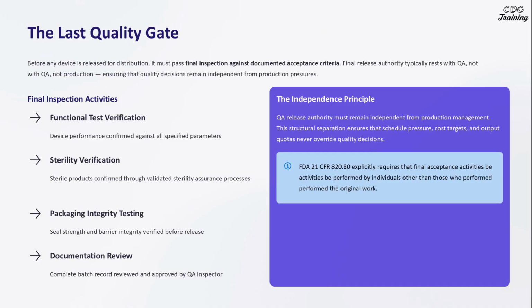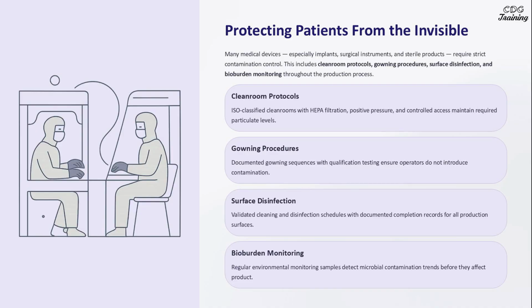Before a device is released, it must pass final inspection against documented acceptance criteria. This ensures that quality decisions remain independent from production pressures. Many medical devices require strict contamination control. Cleanroom protocols, gowning procedures, and bioburden monitoring are essential to prevent microbial contamination throughout production.